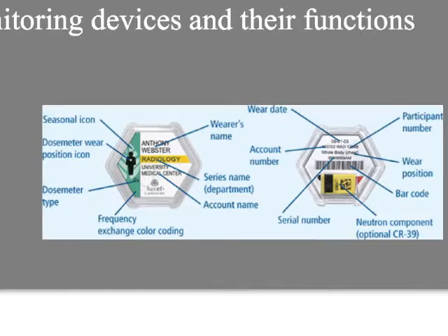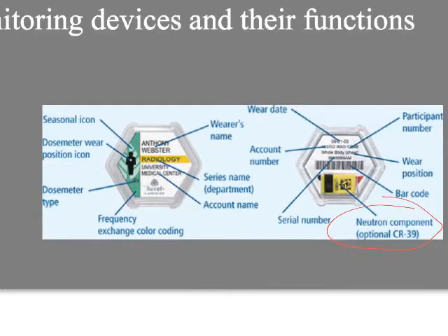If you turn your dosimeter over, there may be a little yellow packet in the window indentation — that's for neutrons. OSLs are not designed to capture alpha particles, neutrons, or positrons. They capture gamma and x-ray really well, and they capture beta well too. If you want to capture neutrons, you need a separate add-on.